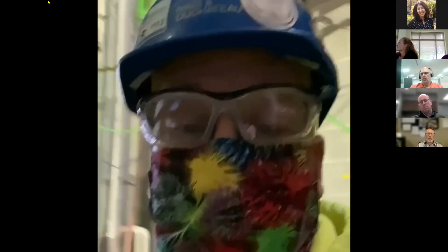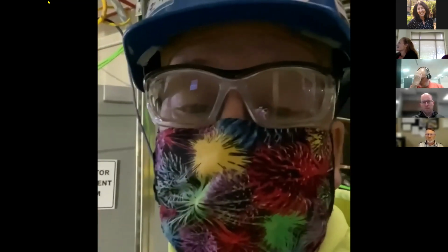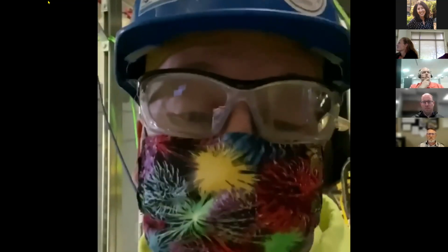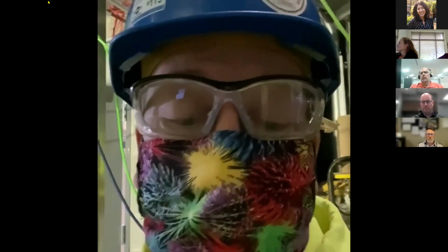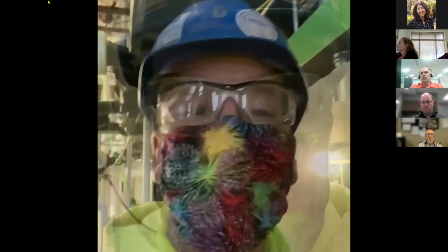So as you can see here by the other fan, it's still running, so those 2 relays are up. And this fan now is slowly speeding up along with its 2 cousins on the other end to make up the difference of the other one. Now, I would say that the units are running a little slower than I would want them to, but this should be a rare instance of this occurring.